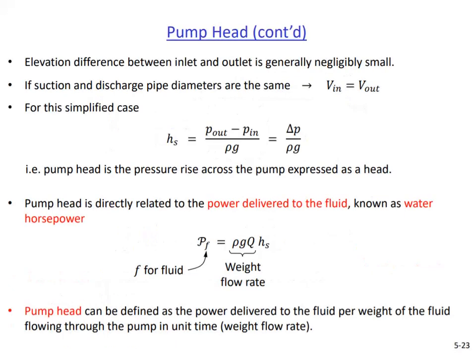In many cases, the elevation difference between the inlet and outlet of a pump is negligibly small, and in many applications the suction and discharge pipes are of the same diameter, resulting in equal average speeds at the inlet and outlet. Under these conditions, the potential energy and the kinetic energy terms of the Bernoulli equation cancel out, resulting in this simplified equation that shows the direct relation between the pump head and the pressure rise the pump creates.